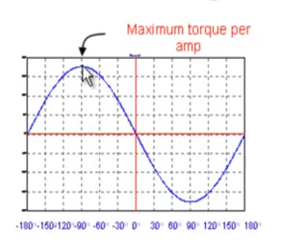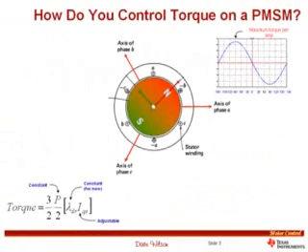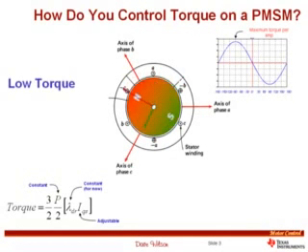The torque produced by a permanent magnet three-phase machine is a function of the angle between rotor flux and the stator current MMF. At zero degrees — when the current MMF vector is aligned with the rotor flux — there is essentially zero torque. At plus or minus 90 degrees we get maximum torque per amp. So in most cases we should orient our stator current MMF vector to be at 90 degrees with respect to the rotor flux. The torque equation then shows torque is proportional to rotor flux times the component of stator current at 90 degrees to that flux.